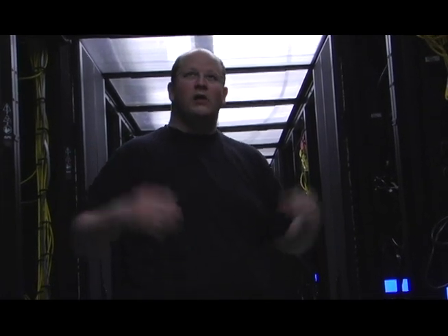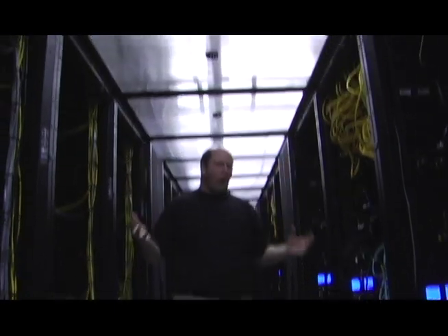This system is actually called a hot aisle containment. We're now standing behind the servers themselves with a roof on top here — all the hot air comes out of the back of the servers and then it's sucked into the air handler units.